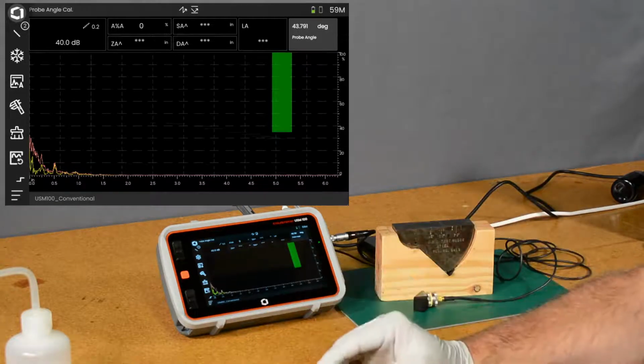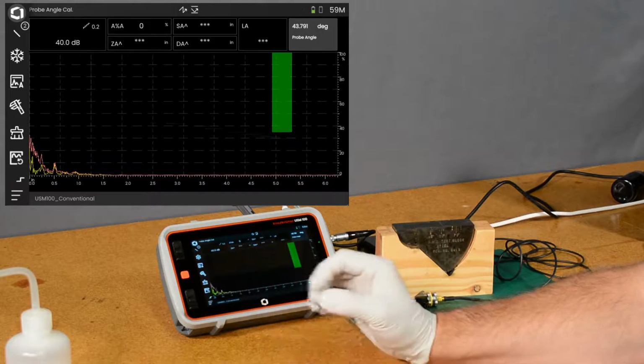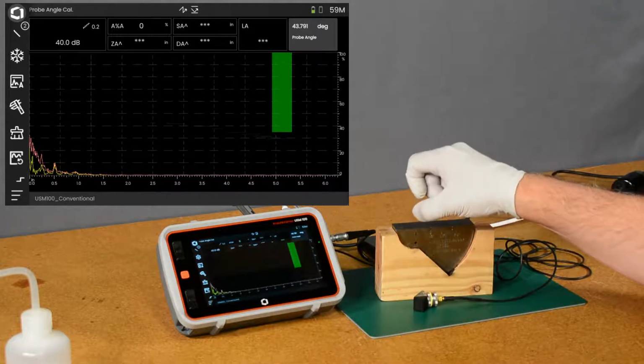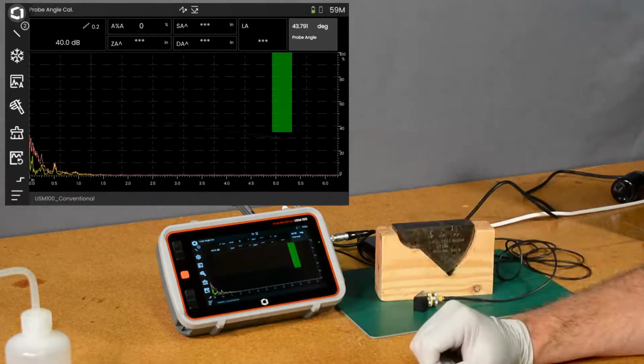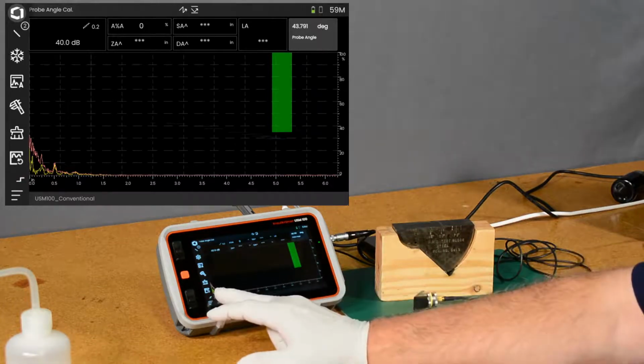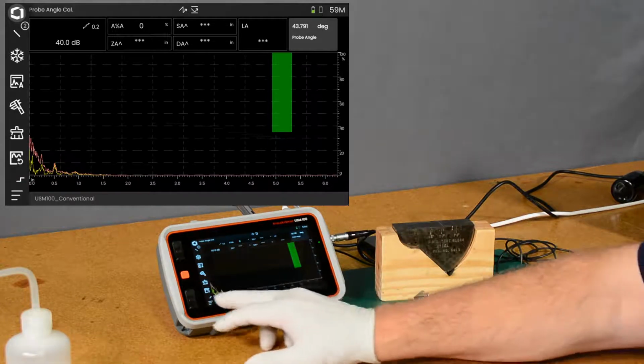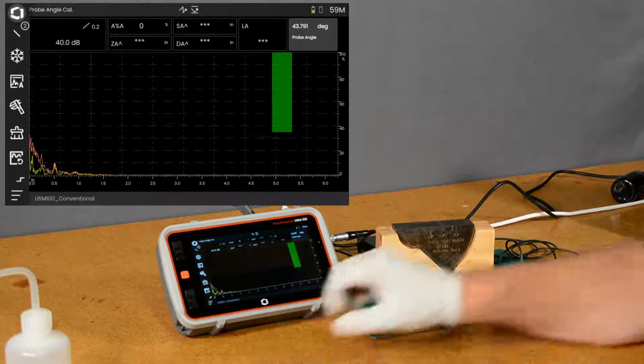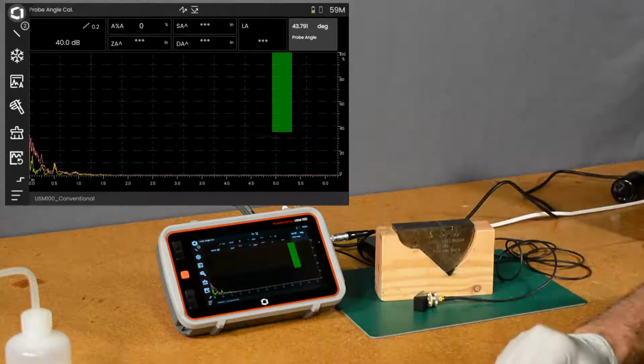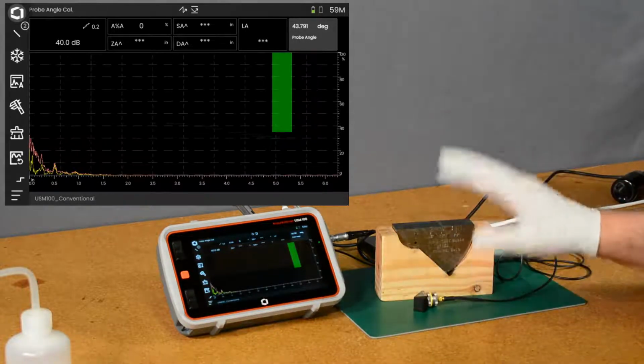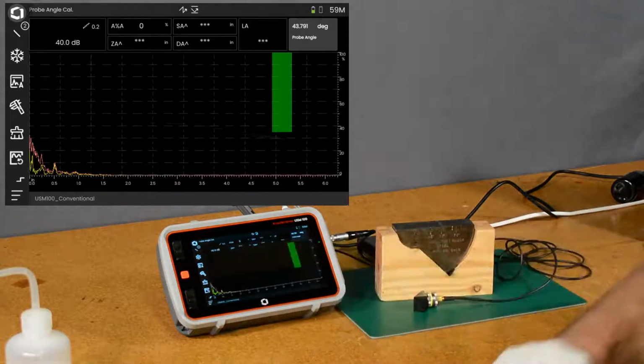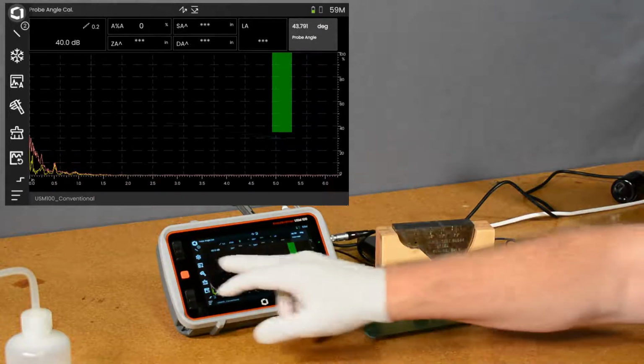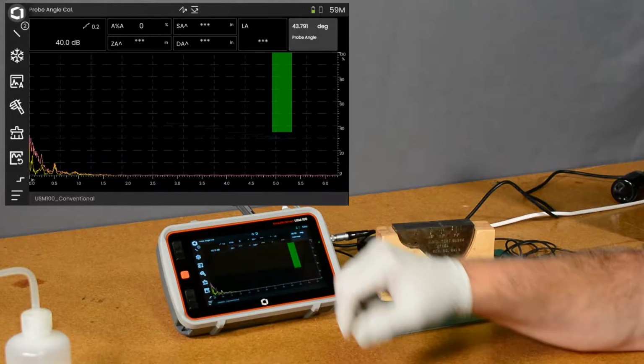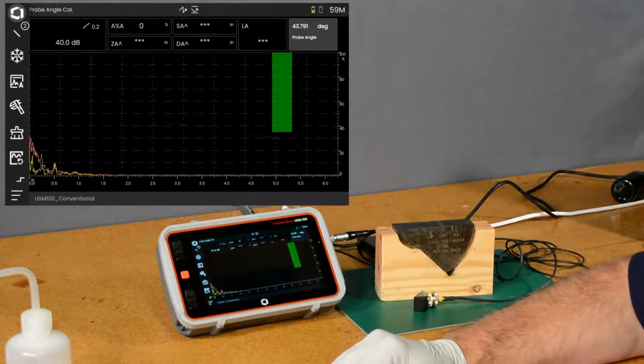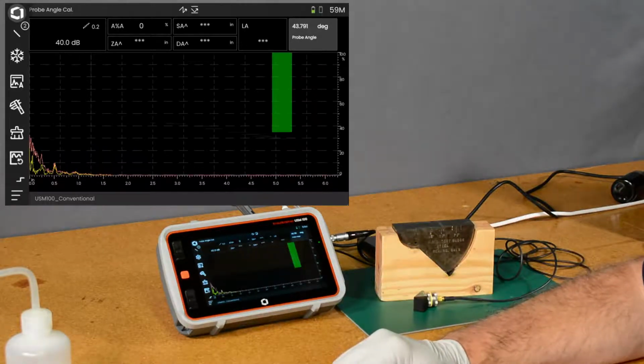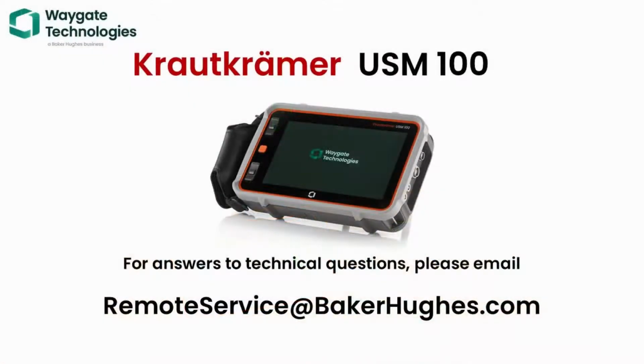In one, we used just the live A scan, peaked it up manually, held it still while we did our calibration. For the other, made use of the envelope mode, start recording our calibration, peak it up with the envelope on. At that point, I can let go of the probe, set it aside, put my gate over the peaked up echo, hit the cal button one more time, and we have our angle measurement. So that's it for auto angle calibration.